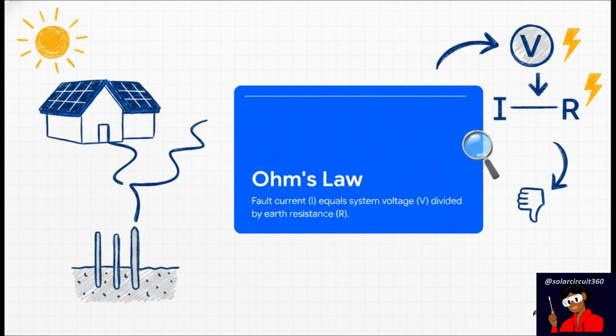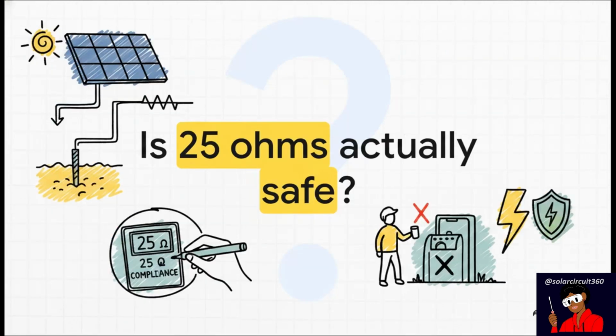Think about your own solar installation for a second. Your system voltage is fixed, right? It's a constant. Therefore, the absolute only variable determining how much fault current can flow is your earth resistance. To trigger those safety breakers, that R value simply has to be low. Which brings us to a really critical question. In the electrical and solar industry, you'll constantly hear that your ground resistance needs to be 25 ohms or less. It's like this magical compliance target everyone aims for. But if you hit exactly 25 ohms, are you actually safe? Does hitting a basic compliance number guarantee that your equipment won't become a lethal hazard during a fault?